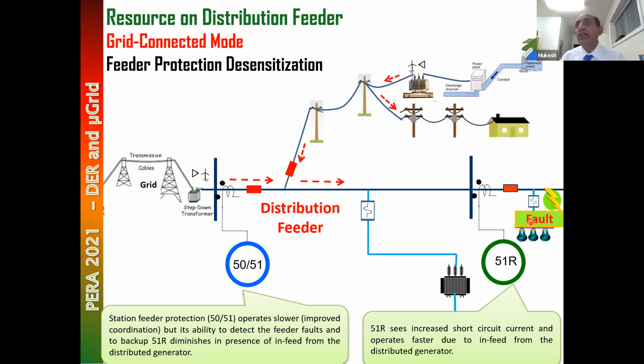So typically, at least in my experience, except for one time out of hundreds of cases where I found a phase desensitization here, in 99.9999% of cases there was no phase fault concern. There was always a ground fault concern. And I'm going to tell you how to resolve the ground fault concern later on, in just a few minutes.